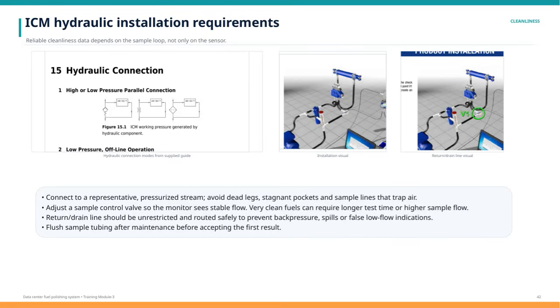Let's talk about the key requirements for installing the ICM hydraulic system to ensure accurate cleanliness data. First and foremost, it's important to understand that reliable cleanliness readings depend largely on the sample loop, not just the sensor itself. This means that how you set up the sample collection path can have a big impact on the data quality. When connecting the hydraulic system, make sure to tap into a representative pressurized stream. Avoid any dead legs or stagnant areas in the sample lines, as these can trap air and give misleading results.